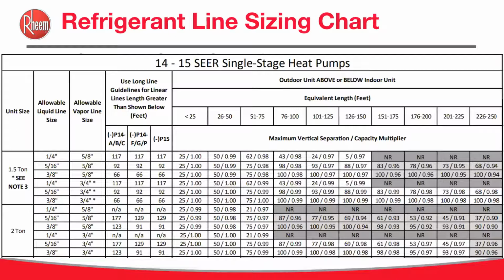Also, when choosing lines for variable speed units, it is important to remember liquid lines are typically sized for full capacity of the unit. And suction lines are sized for minimum capacity. This is to keep pressure drop to a minimum, but maintain oil return when the unit is running on the lowest compressor speed. As we know with our systems, we do not require oil traps with R410A and POE oil. So our systems do not require oil traps as previously with R22. Somebody told me this was because mineral oil is lazy, whereas POE oil isn't. So it stays up with the refrigerant and due to the velocity.